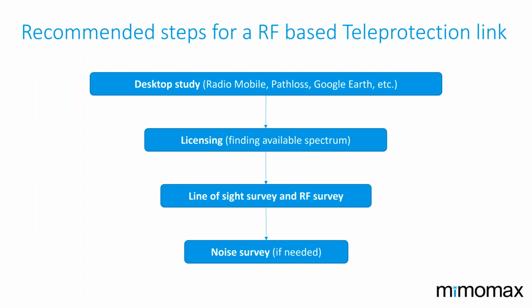And the last thing is the noise survey, somewhere within there, and potentially between vetting that the link is viable and the licensing is making sure you're comfortable with the MIMO equipment, and that you've had a chance to demonstrate, exercise, or evaluate that on the bench with the teleprotection equipment that you will be utilizing. So it's important to make sure that before we go into the field or do anything - and this is typical practice in any case - that we've had a good solid bench test and made sure everything's working as it should be.